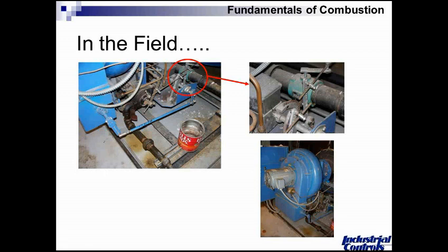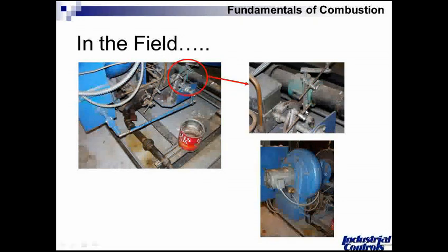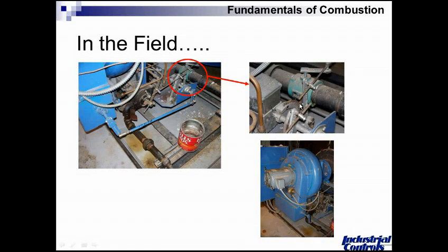Going back to our combustion control side of this boiler, there is a cam which has a mechanical contour to it. On the arm here, which is spring loaded, there is a roller which follows that contour.